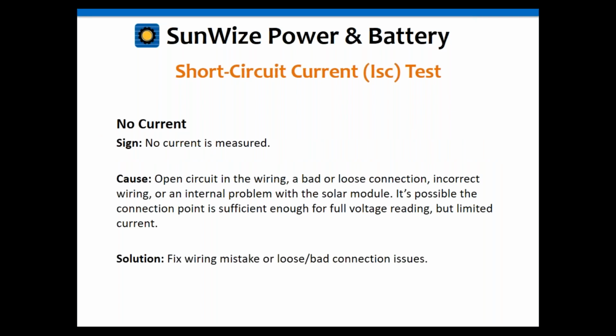Again, let's look at some of the things you can find. Again, no current. Obviously, there could be an open circuit or a loose connection in there. As I mentioned before, it's a common problem with thermocycling. So you just want to fix that problem, whether it's tightening the terminal or replacing the bad connection or wire.